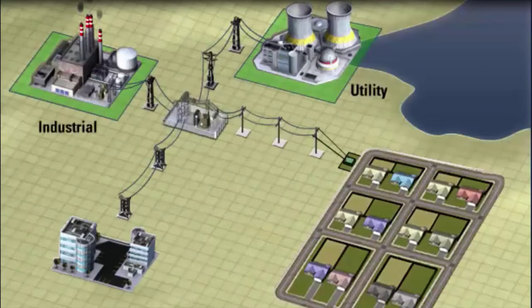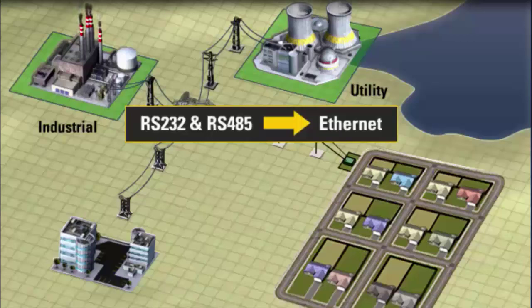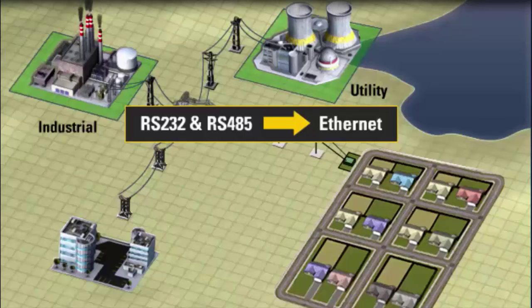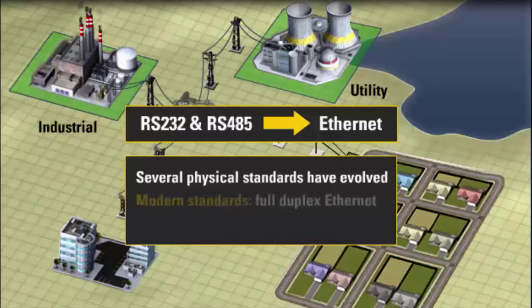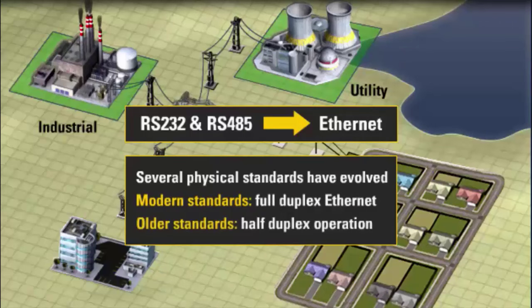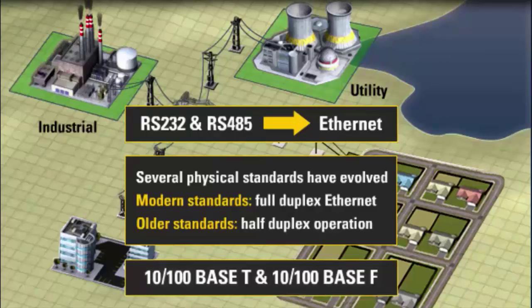Many advancements in Ethernet LAN hardware have created high quality, robust, and multi-vendor compatible hardware that is readily available almost anywhere in the world at relatively low cost. Larger industrial and utility power applications have already migrated or are migrating from older proprietary RS-232 and RS-485 based LAN technologies to Ethernet. Over the years, several physical standards have evolved. The modern standards support full-duplex Ethernet, while older standards support half-duplex. The two most popular physical layer standards are 10/100 Base-T and 10/100 Base-F, both supporting full-duplex operation.